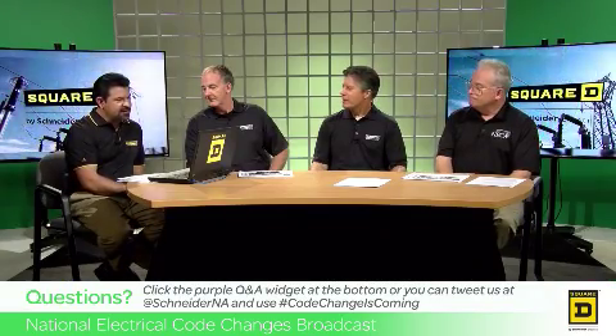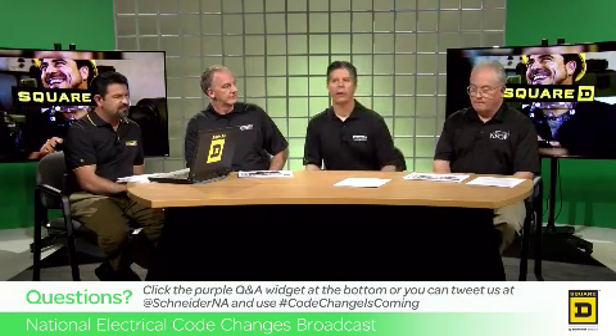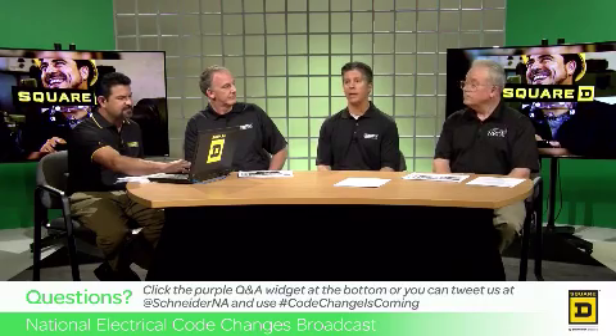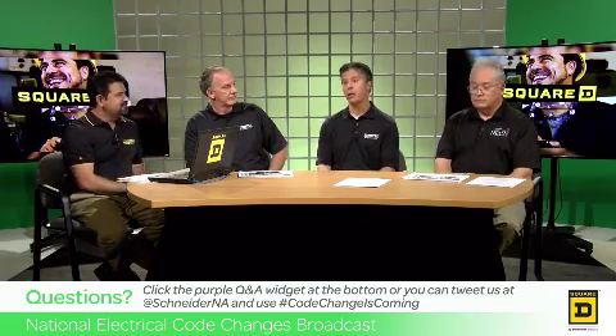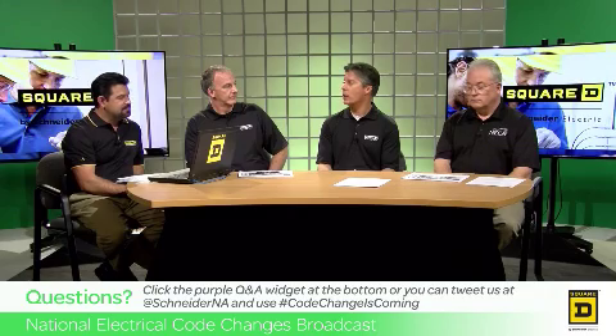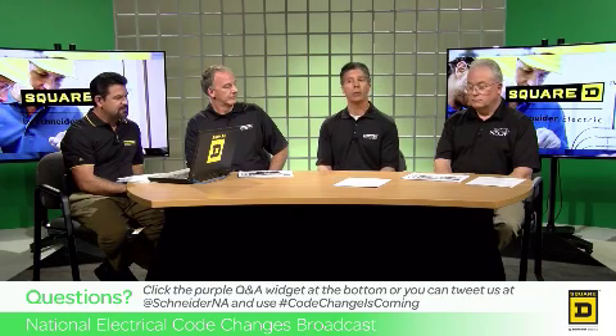Great. Got another 110.16(B) question. I see that arc flash hazard marking in 110.16(B) includes the date the marking was applied. What is the significance of including the date, and does it mean marking is required to be updated on some interval? So I'll take that one. The date is to give you an idea of when the available fault current and associated clearing time were determined. Changes do happen to these systems. The utilities change the available fault current, and those types of changes to your power system need to be incorporated and those numbers reevaluated.